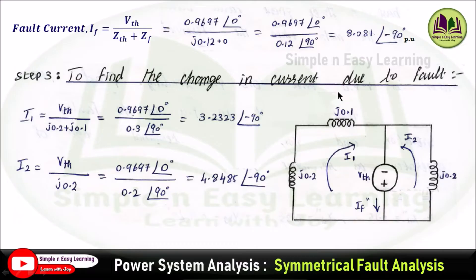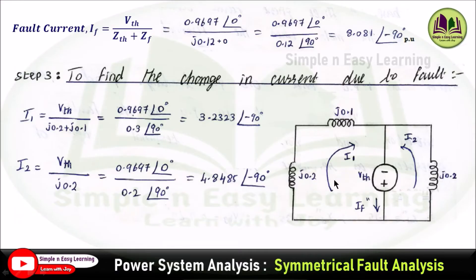Step 3: Find the change in current due to the fault in other parts of the system. The procedure is to fix the voltage source in reverse polarity and remove all other sources. With V_Thevenin placed in reverse polarity at the fault location, current I1 flows in the generator loop and I2 flows in the motor loop. I1 equals V_Thevenin divided by (j0.2 + j0.1), and I2 equals V_Thevenin divided by j0.2. Substituting values gives the currents I1 and I2, which are the currents in other parts of the system due to the fault.